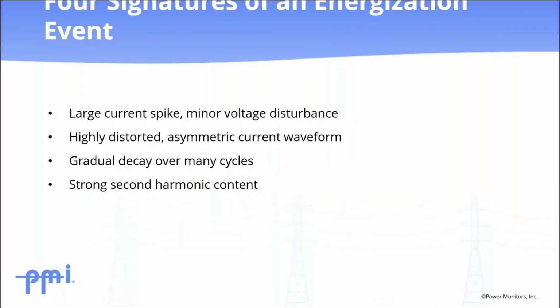So when you're reviewing a PQ recording, what are the tells? There are 4 signatures to look for. A large current spike with only minor voltage disturbance. Faults usually slam the voltage down at the same time the current jumps up. Energization typically does not. Highly distorted, asymmetric current. During an energization, one half cycle of the current waveform can be much larger than the other, and you'll see a clear lopsided shape that you don't see in faults.